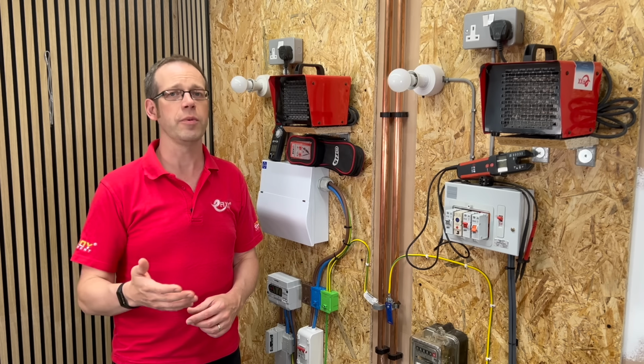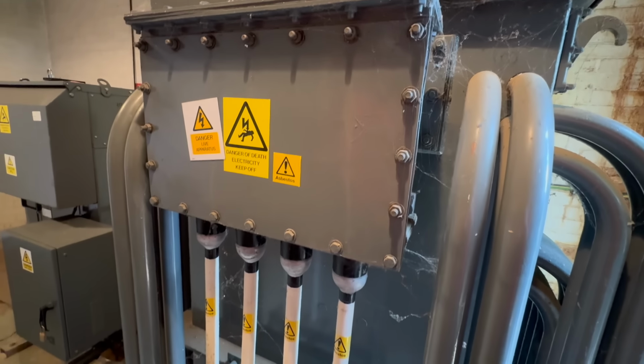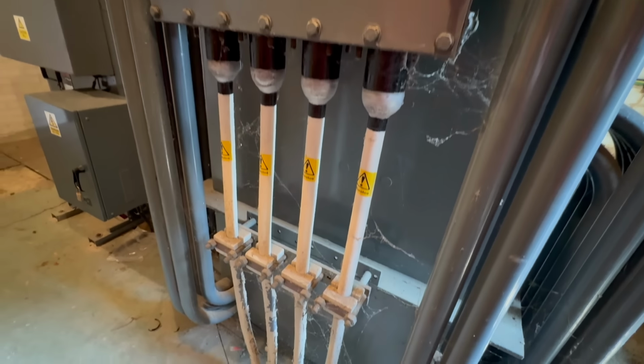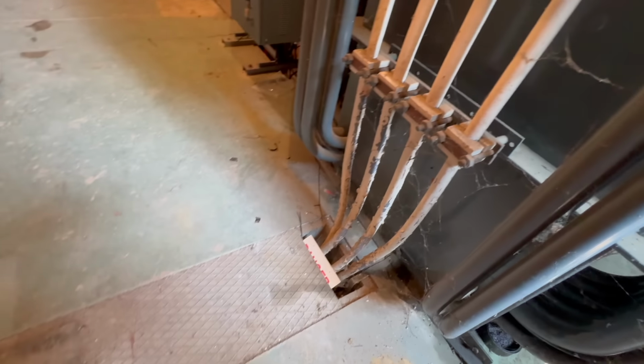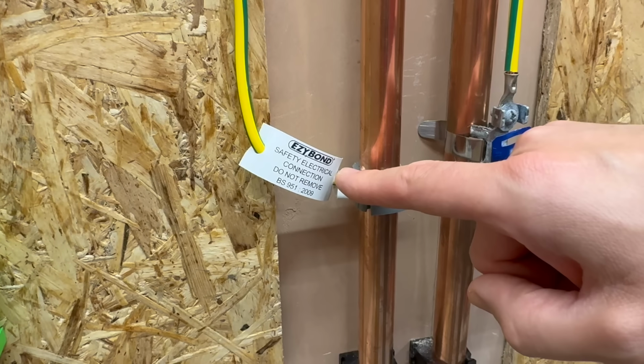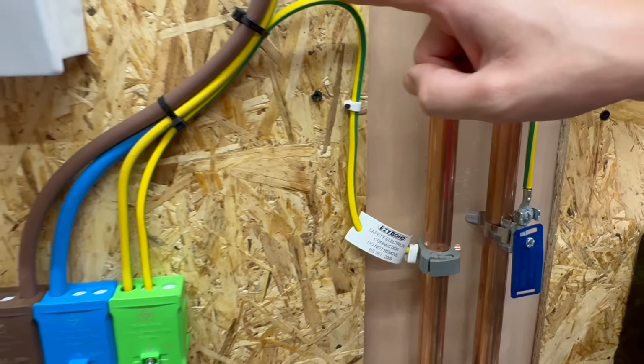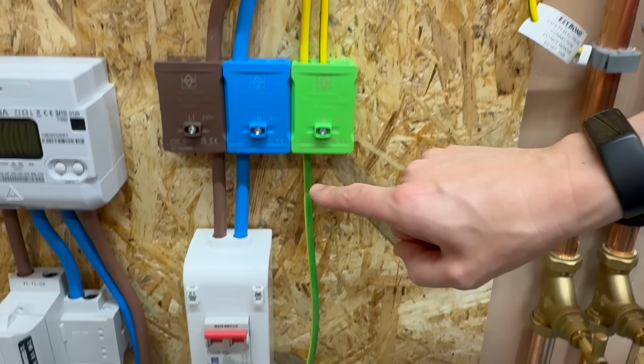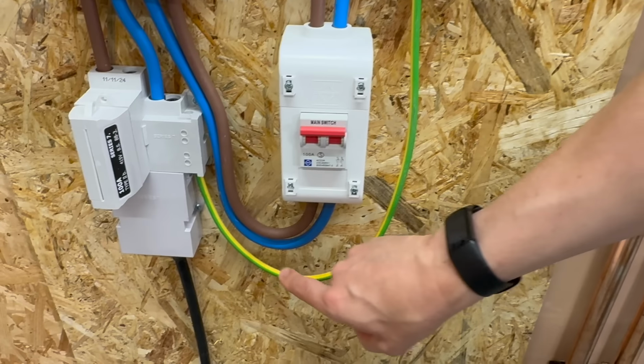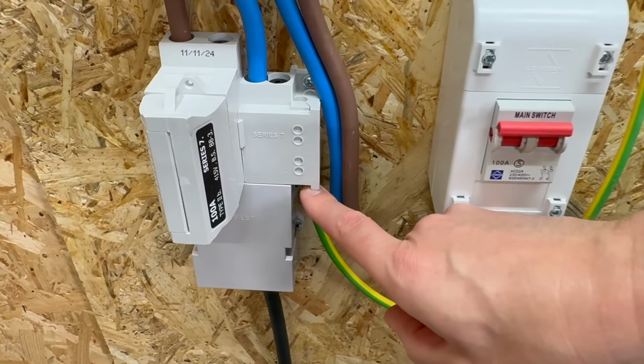It's worth noting that some of the current will find its way back to the transformer via the general mass of earth. However, as the path back will likely have a relatively high resistance and the path back via next door's earthing arrangement will be relatively low, the current will split in inverse proportion and the bulk of it will go via the low path. This can still become a problem even when we've got a plastic incomer.